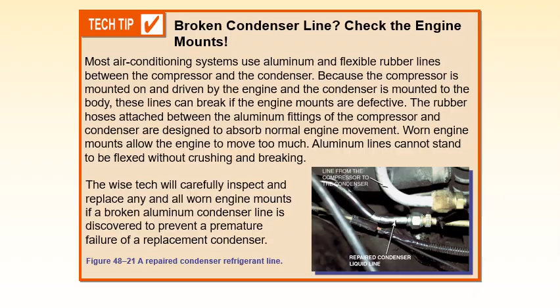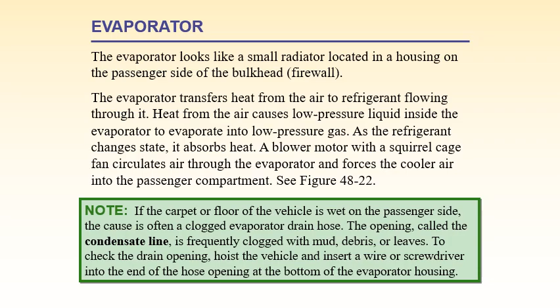Next important thing is the evaporator. The evaporator looks like a small radiator and it is located inside the housing on the passenger side. The evaporator transfers heat from the air to the refrigerant which is flowing through it, and this air is to be circulated into the passenger cabin. Heat from the air causes the low pressure liquid inside the evaporator to evaporate into low pressure gas. As the refrigerant changes state, it absorbs the heat. The blower motor with a squirrel cage fan circulates the air through the evaporator, and this air is forced as cooling air to flow into the passenger compartment. So this is the function of the evaporator.